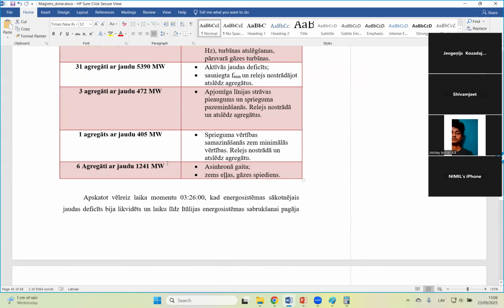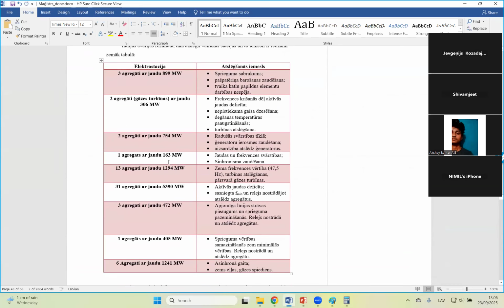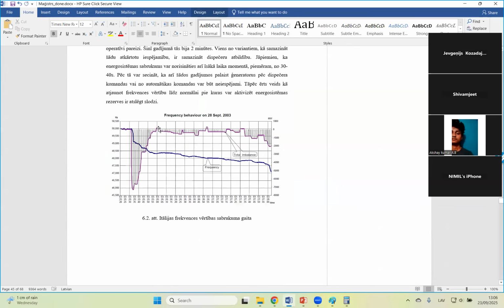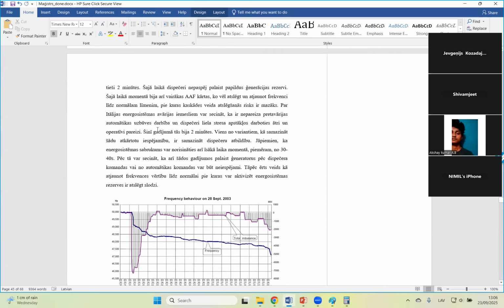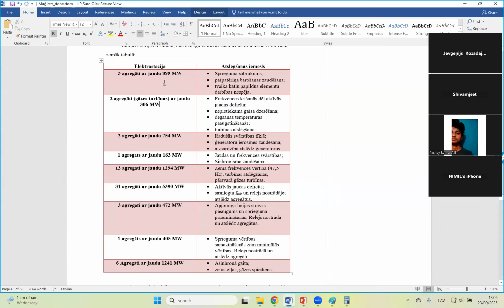And here is a table, a very interesting table, that describes what I said last time, that if we have low frequency, we lose power generators. And here is the list, the number of generators with their power that we lost after the system is rebalancing. No, when the system comes back to the balance. Due to the low frequency, we lose all these generators. You see, this is a total power. Okay, this is 31 generators with a total power of almost 6 gigawatts lost due to their own protection. No, because the frequency was too low.